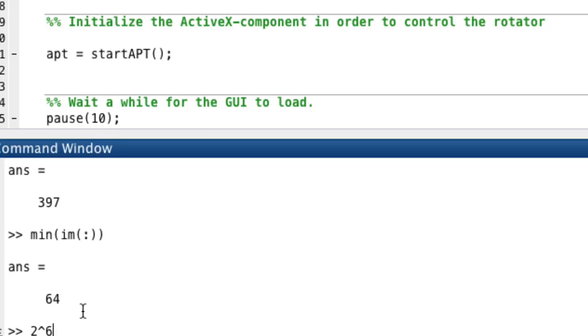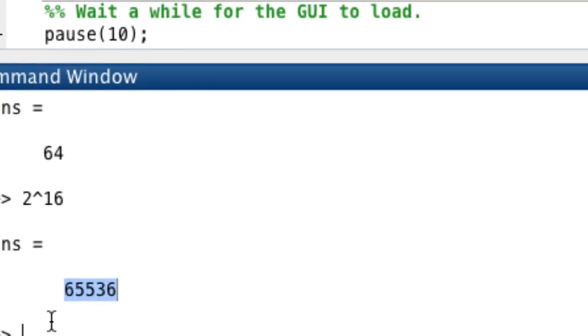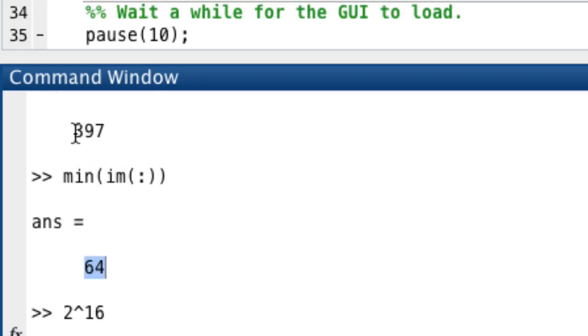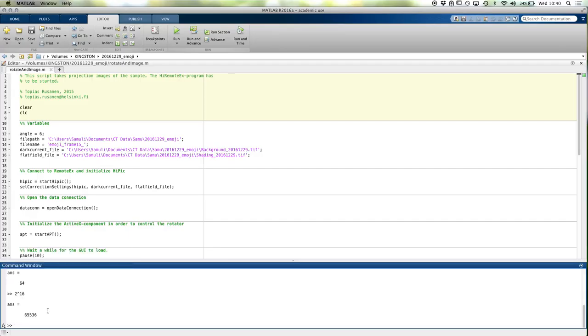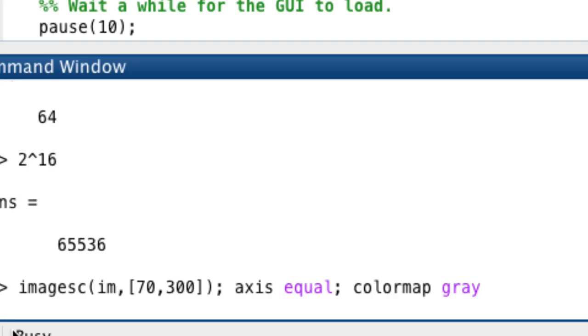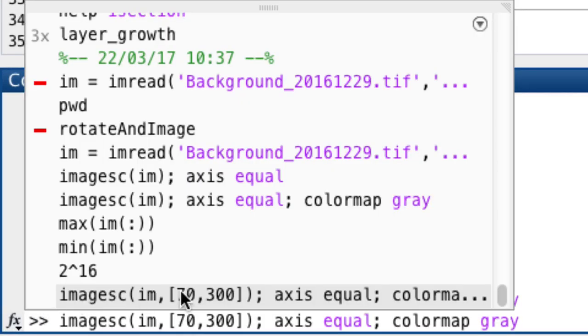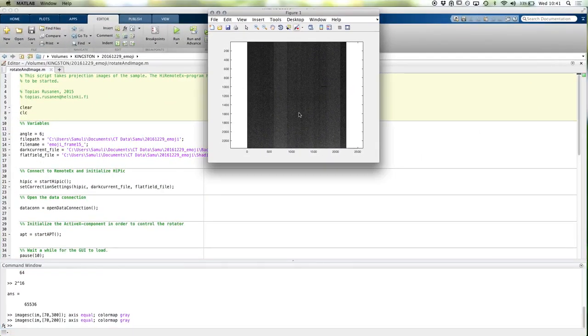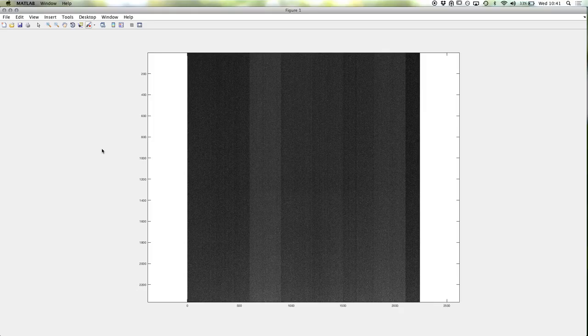The possible range in the image is 0 to 65536, however the image only has values between 64 and 397. So let me show it — something like 70 to 300, let's see how this looks like. Now you see something: something's going on here, it has this kind of weird stripes. Let me reveal that this image is actually taken without any x-rays on.